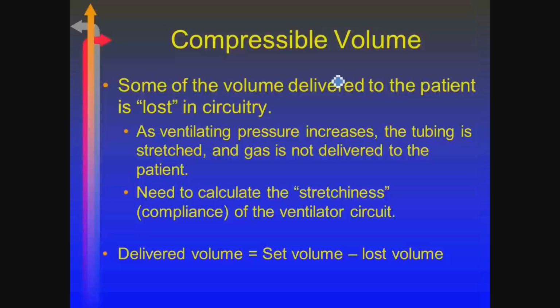All right, let's talk about that concept of compressible volume. As I mentioned, when a tidal volume is delivered from the machine, it puts out a set amount of tidal volume. Some of that volume, though, doesn't go to the patient. It just stretches the circuitry. So there's a small amount of what we're going to call compressible volume that's lost. So ultimately, the delivered volume is whatever is set on the machine, less whatever is lost, okay?